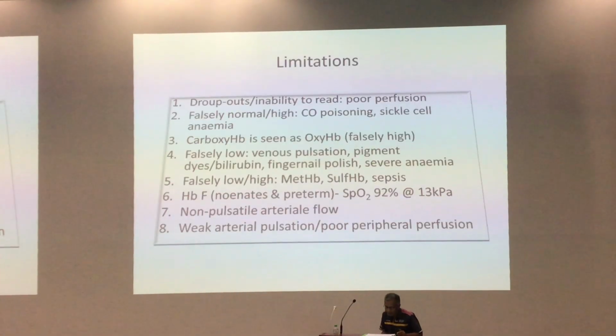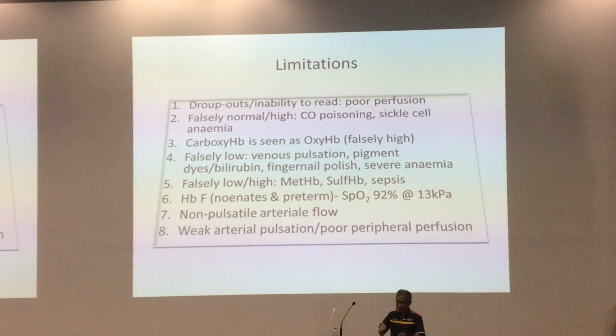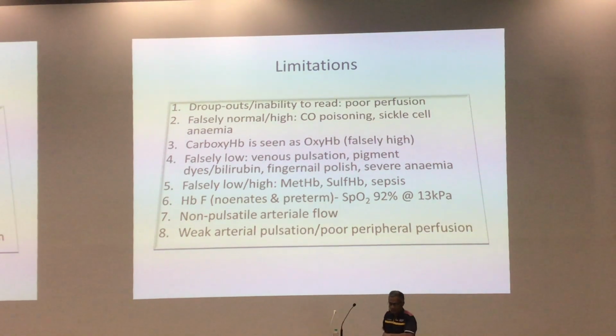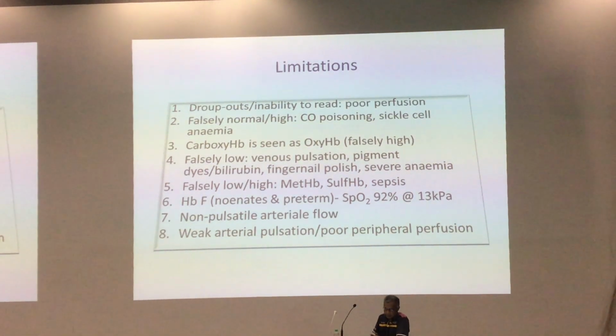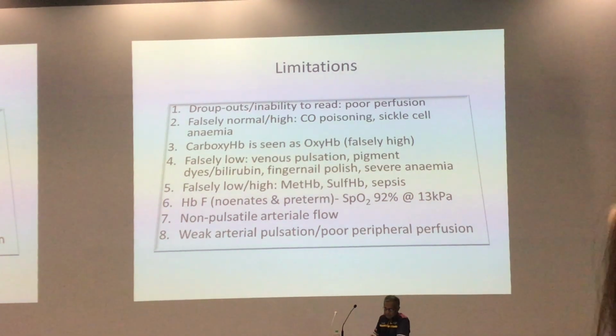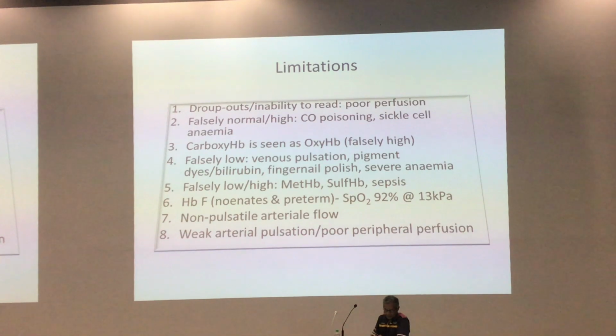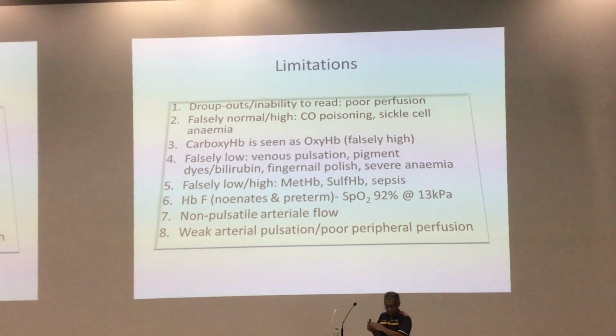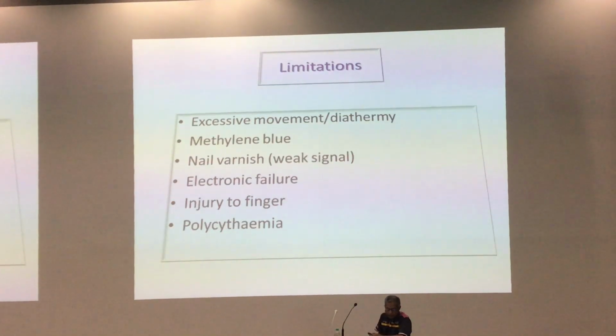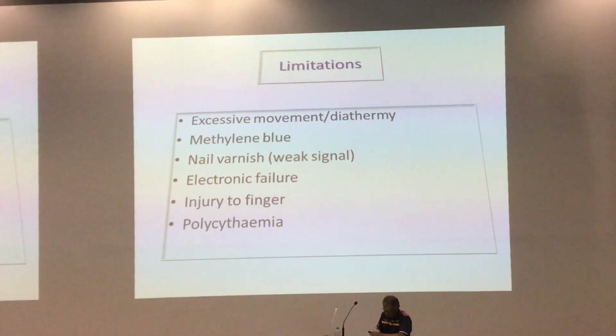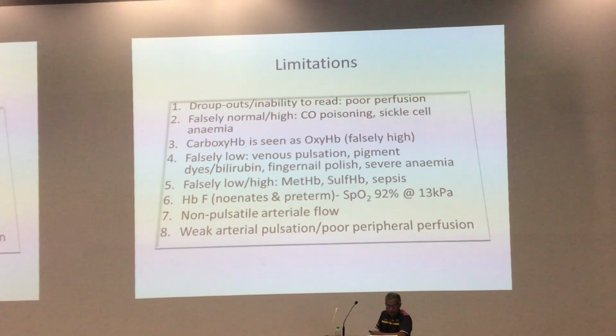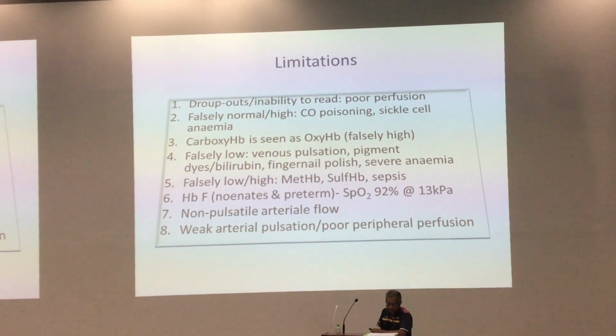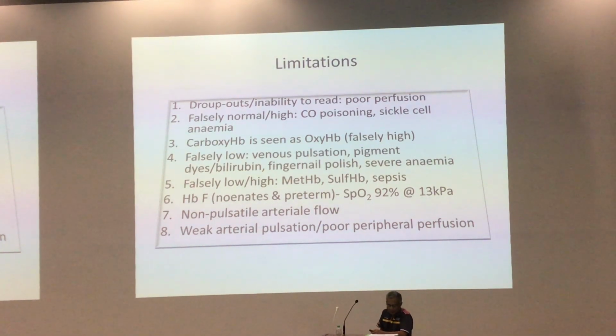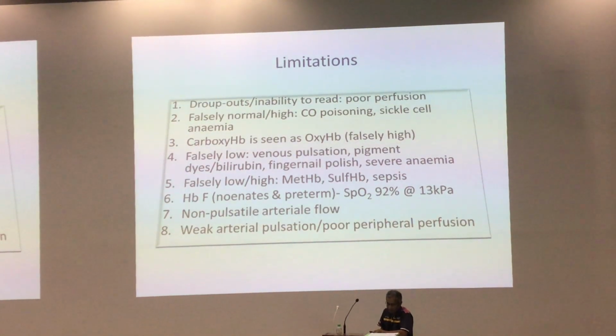Now, this is the detail. Now, these are the limitations, where you get inaccurate SpO2 measurement. For example, with carboxyhemoglobin, you get falsely high readings. For example, if you use nail polish, a weak signal, right? You might get a low measurement. What else? Methemoglobin, it can give both low and high measurements. Weak arterial pulsation, low measurement. Or peripheral vasoconstriction, low measurement.